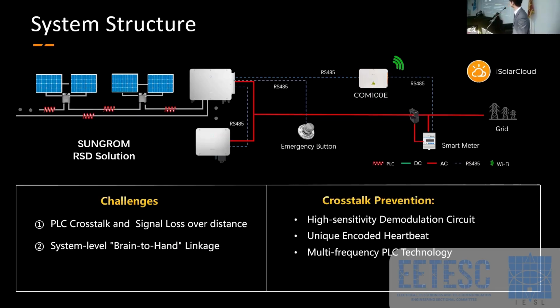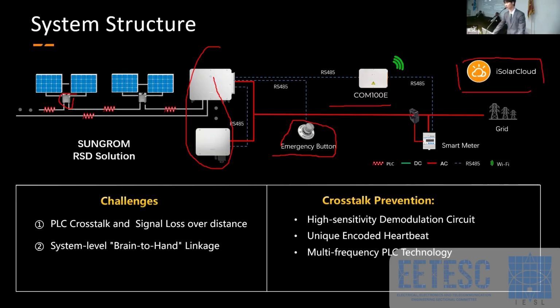And here's the system structure of the Sungrow solution. Let me introduce it from the left. Here are the PV panels, and we install the rapid shutdown unit. It's connected to the inverter, and the inverters are connected in parallel. We provide a separate emergency button for the owner to use, like when you want to do maintenance or in some emergency situations. The firefighters will press the emergency button to cut the voltage. And here is the communication device that is used to upload the generation data to the iSolarCloud. The cloud is a platform, and we provide an open API for the users.